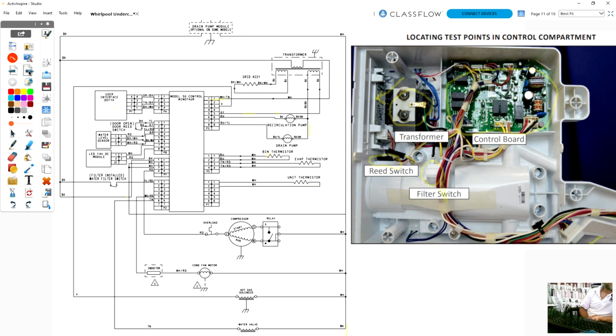How do we troubleshoot this unit besides the diagnostics? We said that we had a water valve problem. On the old ones, the evap thermistor initiates ice harvest, and on the new ones, the water level sensor initiates ice harvest. I'm sorry, I misspoke. If there's no water in the reservoir, let's say the water valve went bad and there's ice stuck on the evaporator, it is possible the water level sensor is not telling the board that enough water has come out, so let's go ahead and fill up with more water. That is in the ice harvest cycle.